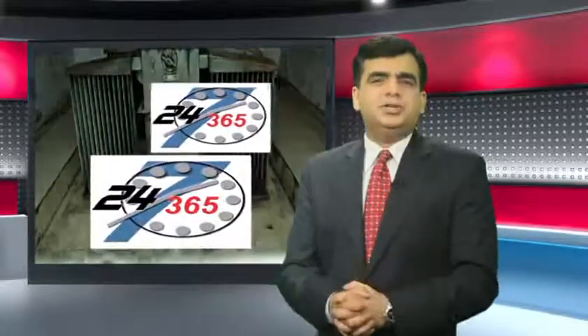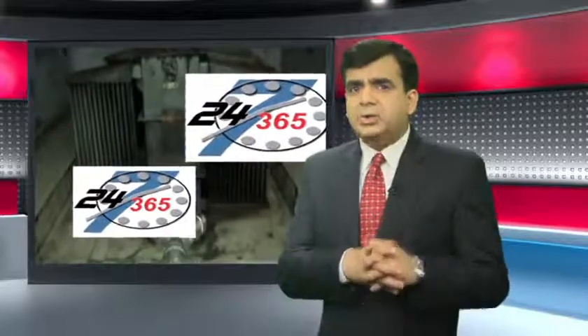The system is on 24/7 and has extended reach due to its flexible tubing to access all areas. It's also environmentally friendly, people friendly, and electrically non-conductive. It also uses considerably less water than a conventional water-based system and evaporates completely in the fire environment, leaving behind no collateral damage. The system is also economical because water as an extinguishing agent is cheap and maintenance requirements are reduced.